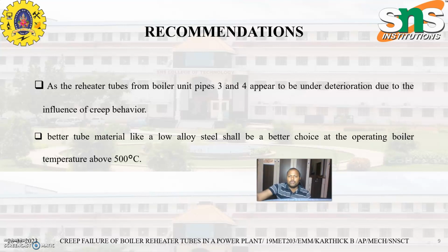Up to creep 2 we can get it resolved, and we can remove the particular material to a safer side, and also use it again with the new tubes. But when it reaches the third stage of creep, it will surely fail at any point. So steel operating at high temperature should be continuously monitored to avoid creep failure.